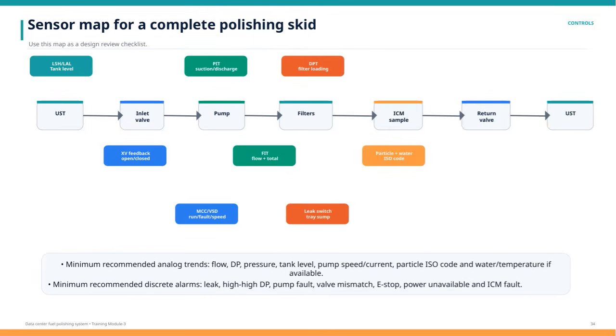Here we have a sensor map designed for a complete polishing skid, which serves as an essential tool during the design review process. This map acts like a checklist, ensuring all critical controls are accounted for and properly integrated. Starting with the controls, key components include the underground storage tank, or UST, inlet and return valves, pump, filters, and the ICM sample point. Monitoring these components is crucial for the system's reliable operation.